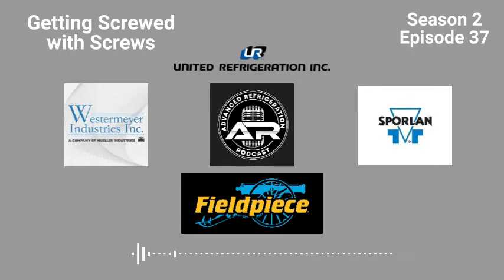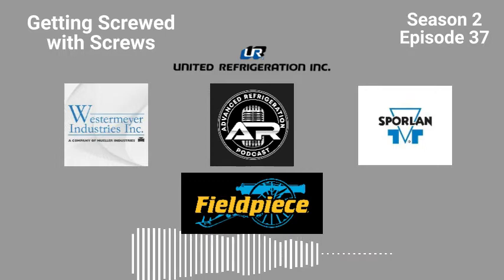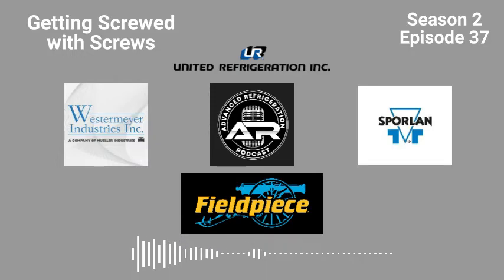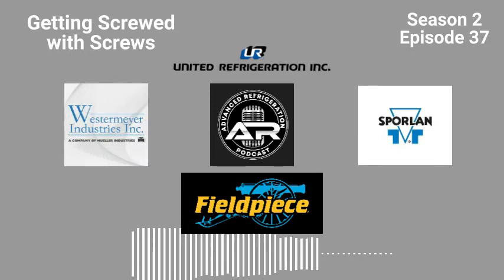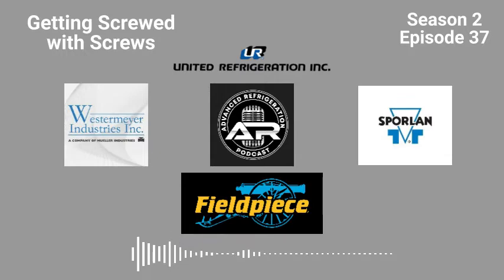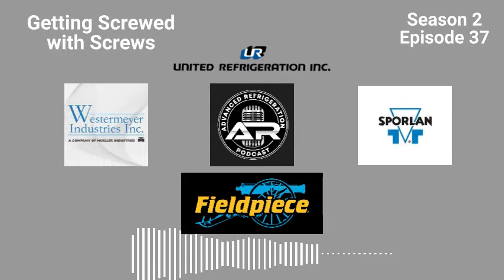Well, running it for a little bit to help drop the suction pressure off, so some of the load came off. Yeah. Whenever it gets above 250, it trips on high head. But okay, what's the control set for? Obviously it's gonna be like 350 or something like that. Yeah. So I'm like, okay, what's going on here? You don't sound right. You could hear it. You've got a high pitched noise going. So I started looking through it, and I'm like, oh no. I already know what's wrong.